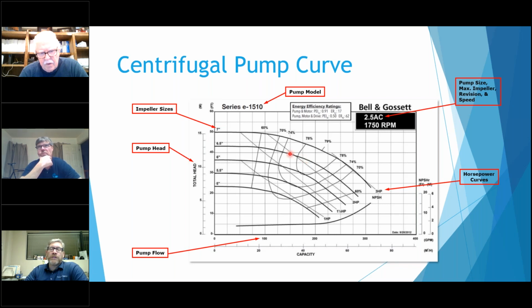So what a lot of people do, if you're using this 6.5-inch impeller, is they want a non-overloading motor throughout the pump curve, so they'll jump it up to 3 horsepower. That way, if you're actually running out here, or maybe you want to run back here and you start the pump up and it's running out in this direction, you're not going to have issues with the motor overloading.